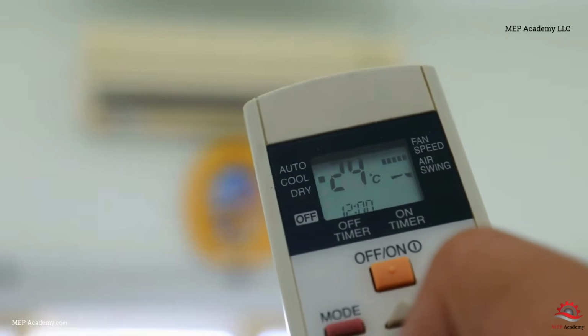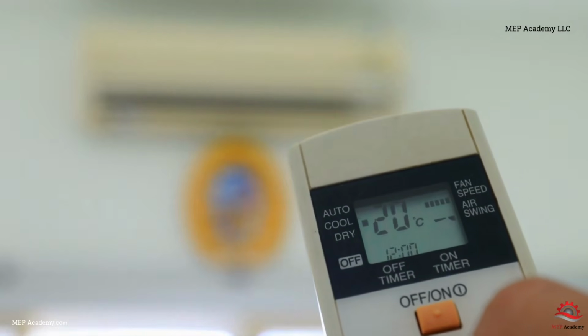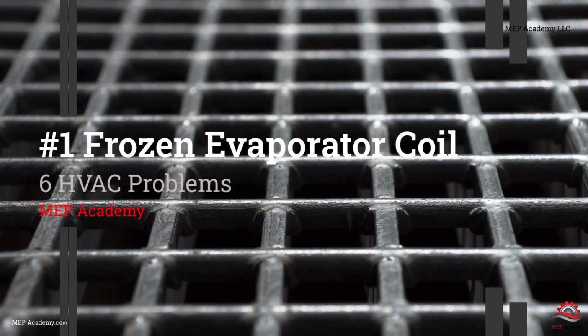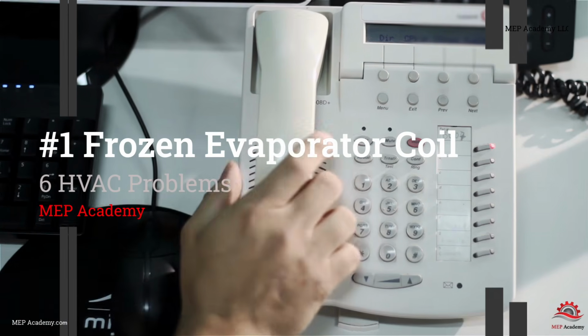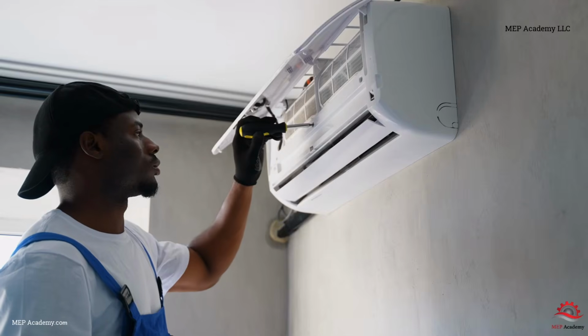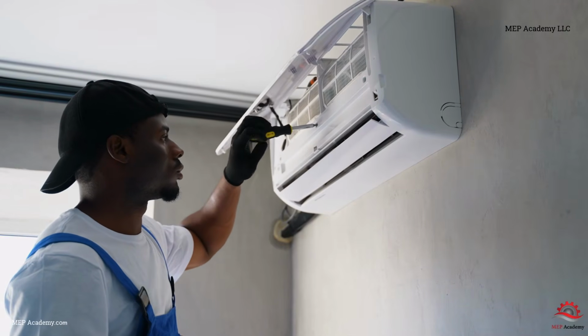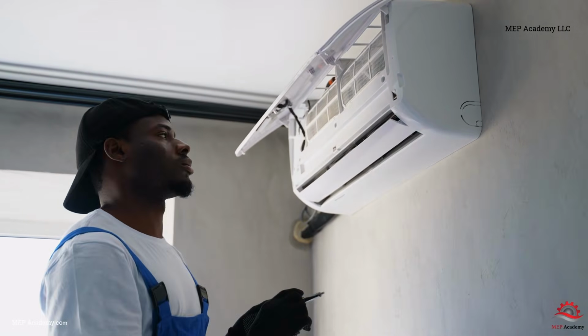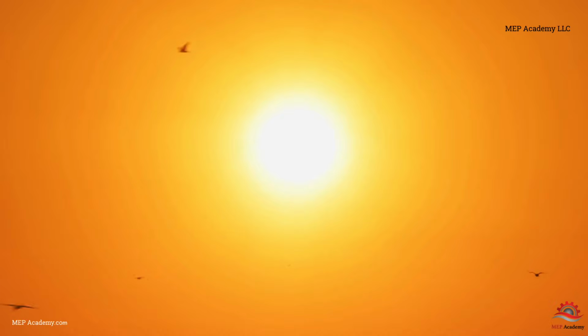Let's start with one of the most common and most misunderstood problems. Problem number 1. Frozen evaporator coils. A customer calls and says the building is warm. You arrive and discover the evaporator coil inside the air handler is covered in ice. Many people assume this means the system is working too hard because it's hot outside. The truth is usually the opposite.